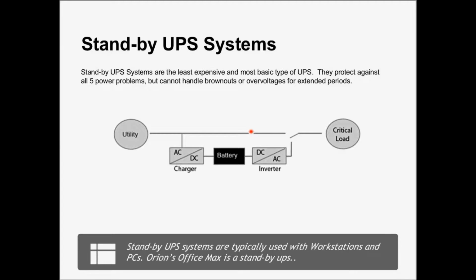The biggest flaw with this design is that if you have a prolonged brownout or overvoltage, it will switch on the battery and then run until the battery gives out, and then it will drop the load. So that's the only real issue with that particular design.